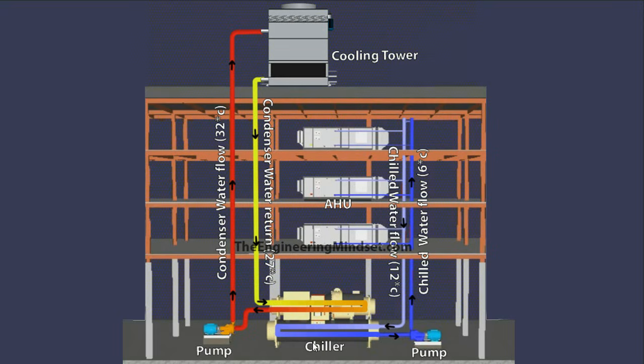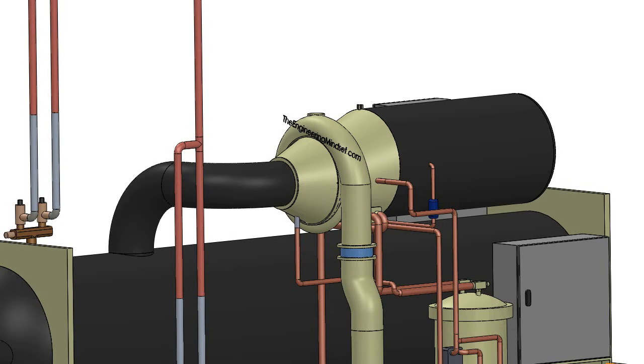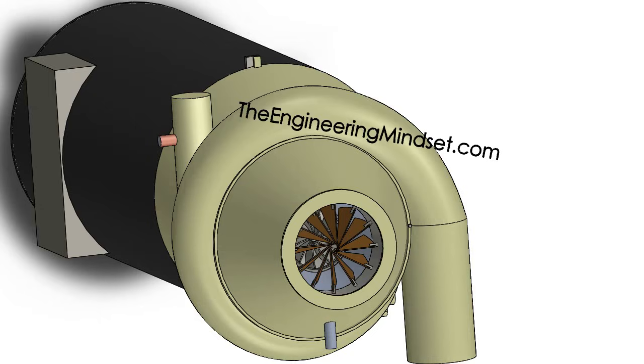This water would go back out at 12 degrees and come back at 12, probably even higher than that, and eventually the chiller would just trip out. So let's have a look inside the compressor, the centrifugal type, and see how it works. So if I just isolate this part of the chiller, and start to strip it down, and we'll have a look inside the components. So here we've got obviously the discharge line coming there, and the suction line would be coming in and entering here where the refrigerant enters, and I've just removed those sections there so we can start to look inside.